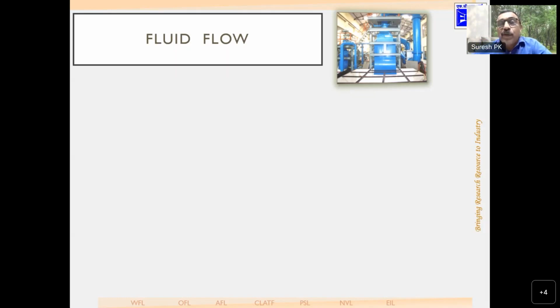Rather, you see, when you make a measurement of a meter or a kilogram, it is something static. But when you're making the measurement of a fluid, most of the time it is flowing. So you are trying to measure the fluid when it is moving. The movement of the fluid can affect the flow meter performance. The fluid conditions, like whether it is high pressure or low pressure, or whether it is flowing in two-phase. Two-phase means a flow with liquid and gas, or gas containing liquid, or a liquid containing gas.